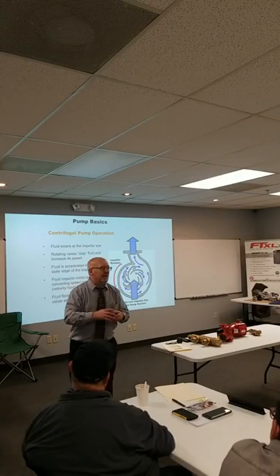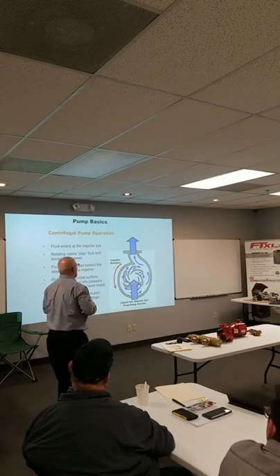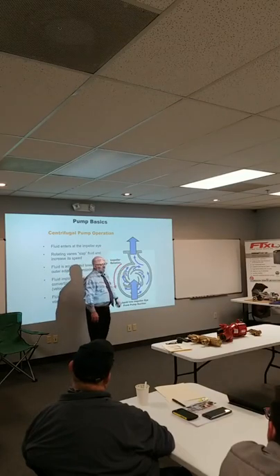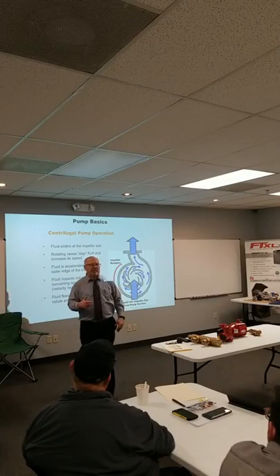Going in the wrong direction does not change the direction of flow. It's the volute or the body that determines the direction of flow. It will reduce your capacity.